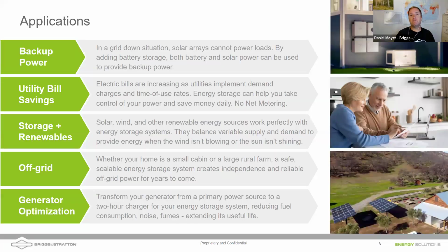So this talk is going to primarily focus on adding a generator to an energy storage system. But unlike a generator, which kind of just sits there as standby backup power, an energy storage system can also provide utility bill savings, right? I talked a little bit about doing time of use rates. Also be able to do peak shaving if that's something that's in your jurisdiction. And then also be able to tie in some of that renewables, right?